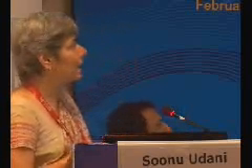And how do these modes help us? What is a dual mode, first of all? It's a mode that takes into account controlling pressure or volume, but controlling one while giving the other, and giving the other while controlling one. And it can be within a breath, so it can switch from pressure control to volume control within a breath, or more commonly it is our PRVC mode, which we are very familiar with, from breath to breath. Let's see how it does this.